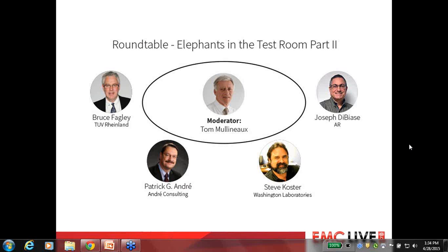Joe, what's your view on this? Well, Tom, my position is that the OATS are still of value in certain situations. One of the main things I believe that can help with consistency across the OATS is with the adoption of the 17025 as a backbone to the lab quality management systems. ISO 17025 has allowed labs to perform, and encourages and mandates them to perform, interlab testing. These tests are performed with a known radiator, so labs can check from each lab the radiated emissions and profile those at specific frequencies, and oftentimes that helps them mitigate any issues they may have amongst each other.